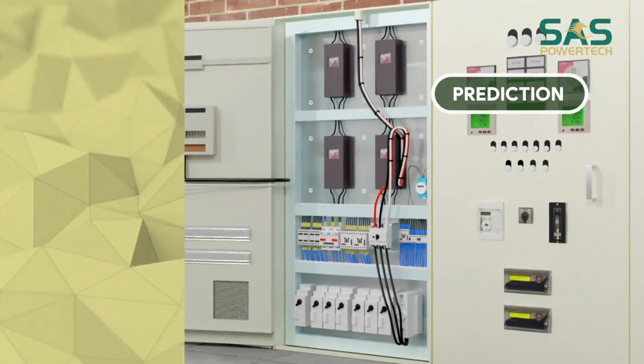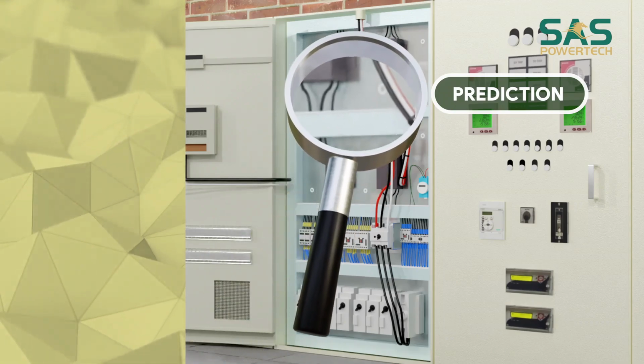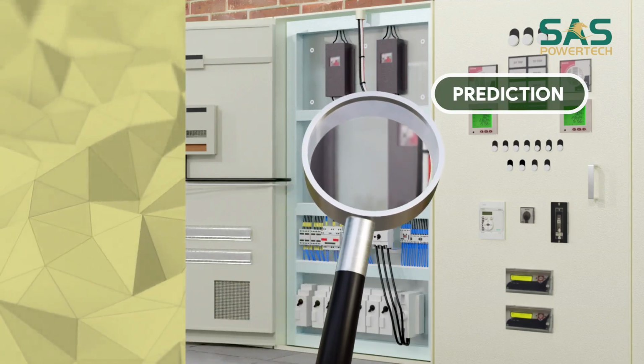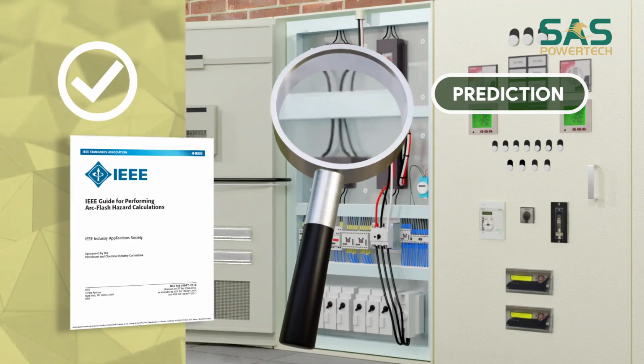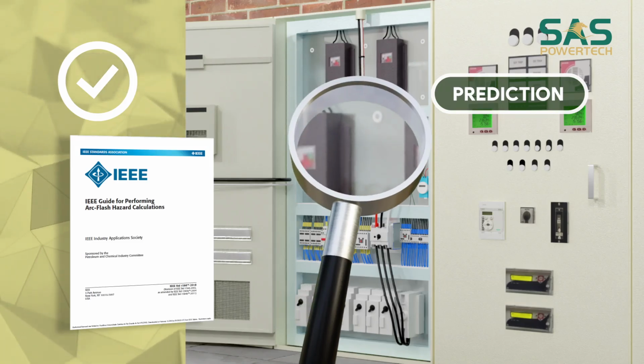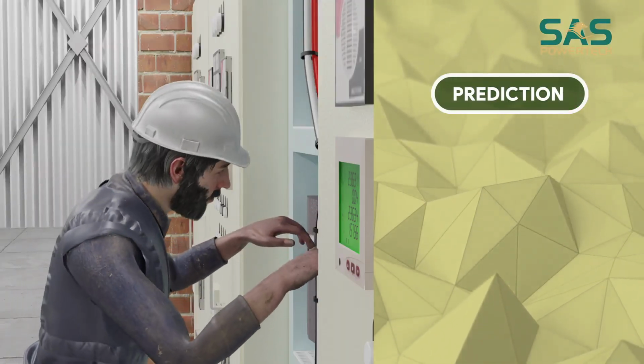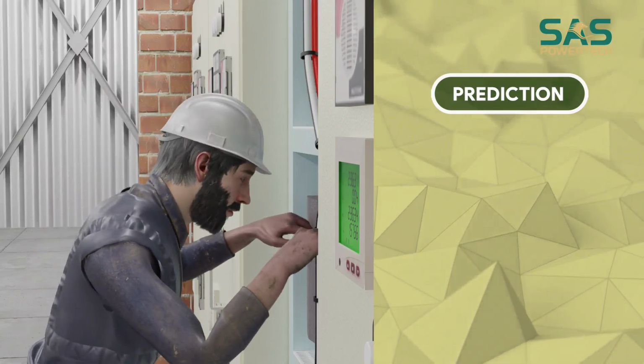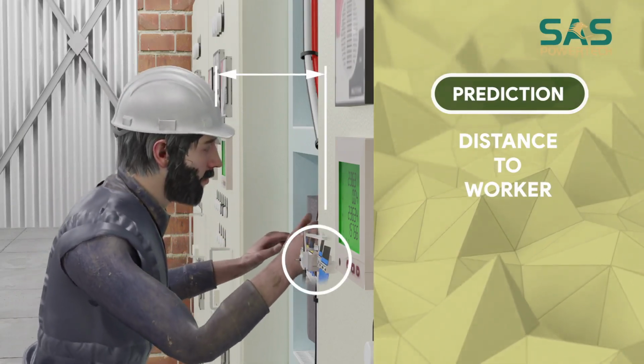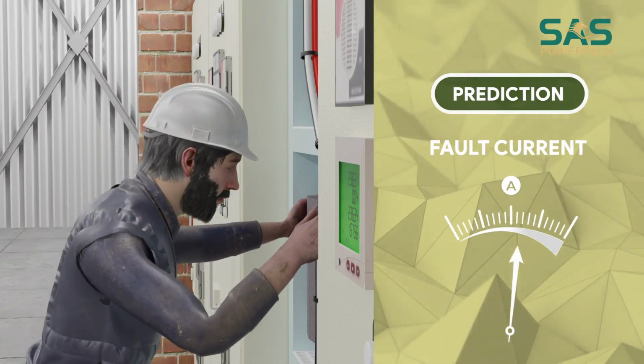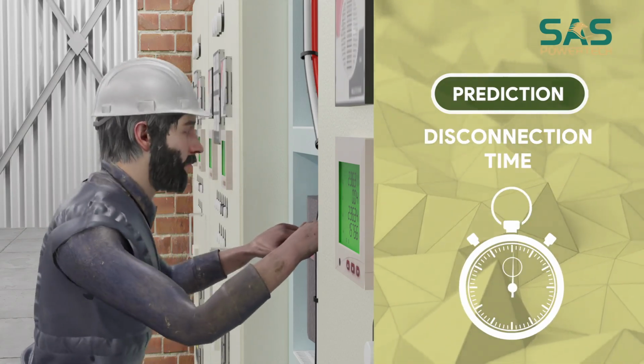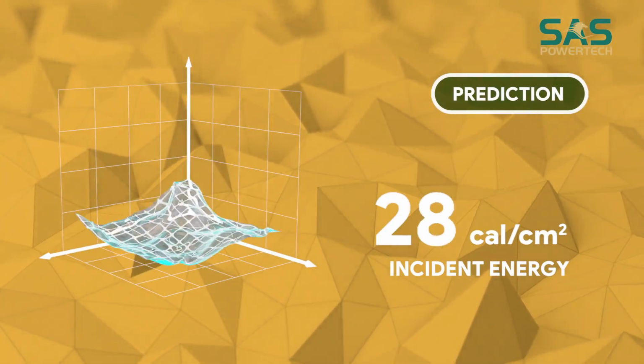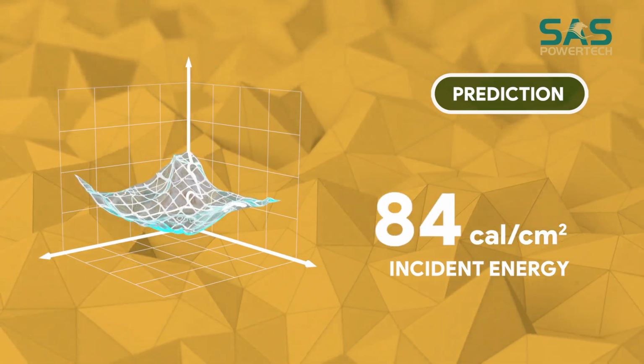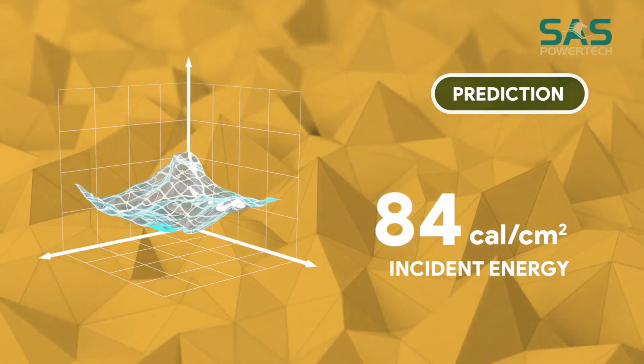Firstly, prediction. After making an initial assessment, we calculate the severity of the thermal effect of an arc flash on a given piece of equipment following the IEEE 1584 standard for performing arc flash hazard calculations. In the case of Kumar's incident, the assessment could have taken 4 factors into consideration: 1. Distance to the worker. 2. Voltage. 3. Prospective fault current. 4. Disconnection time. Computer modeling of these factors results in a value for incident energy. This incident energy is a key component in assessing risk and devising measures to prevent it.